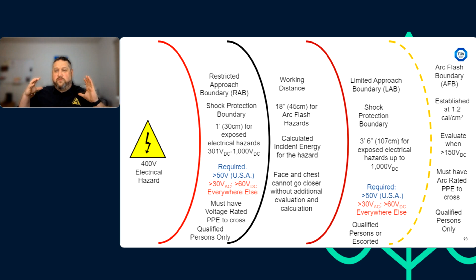Now this boundary, to be honest, in most cases, with the amount of protection we have in a lot of our high voltage systems, the amount of energy that is released is so small that this boundary can sometimes be the closest boundary. So it's a dashed line because it's variable. In a lot of cases, it's going to be inside of this restricted approach boundary, and we don't even have to have additional controls. But that's why we have to evaluate. We have to do a calculation and verify that. We don't want to make assumptions.